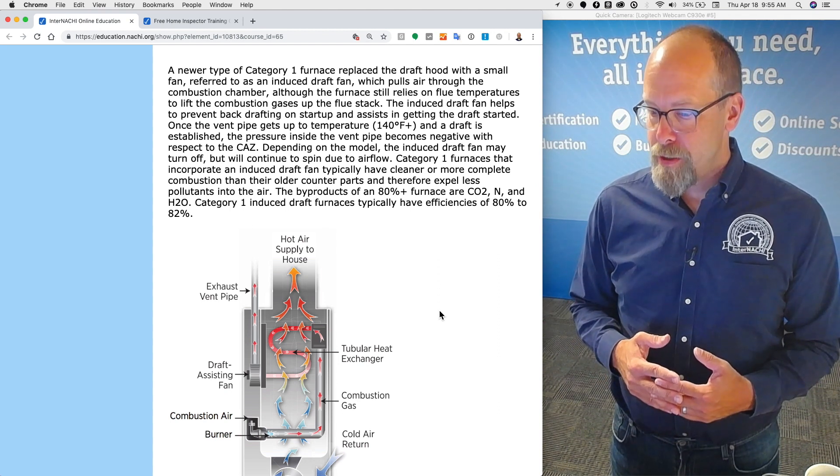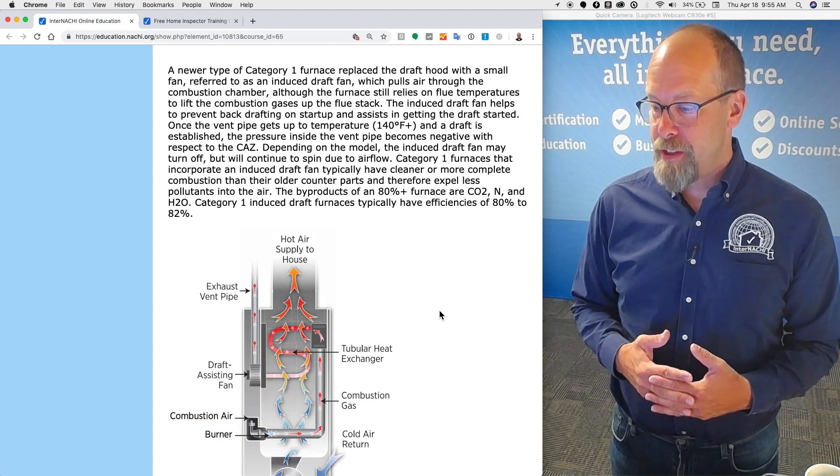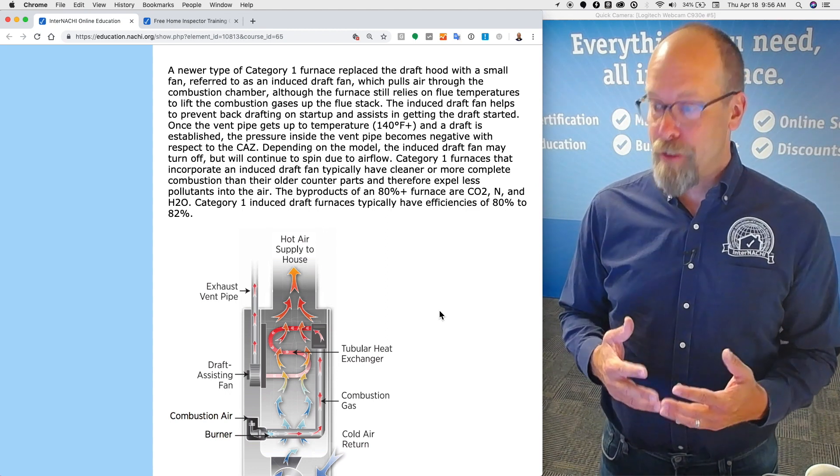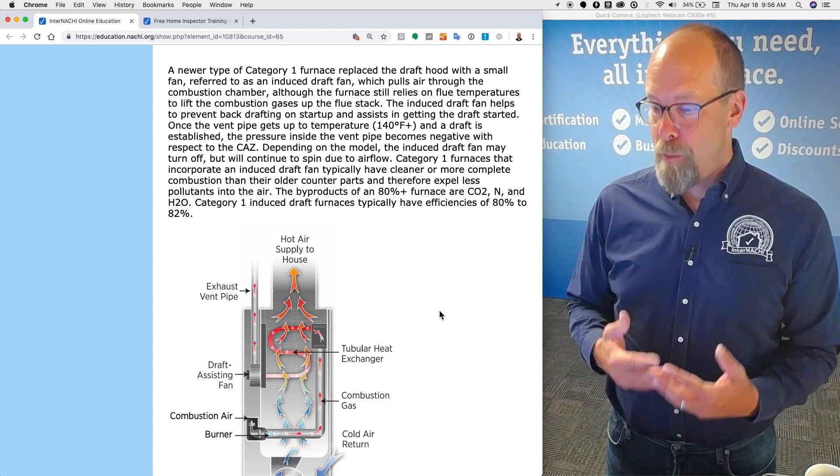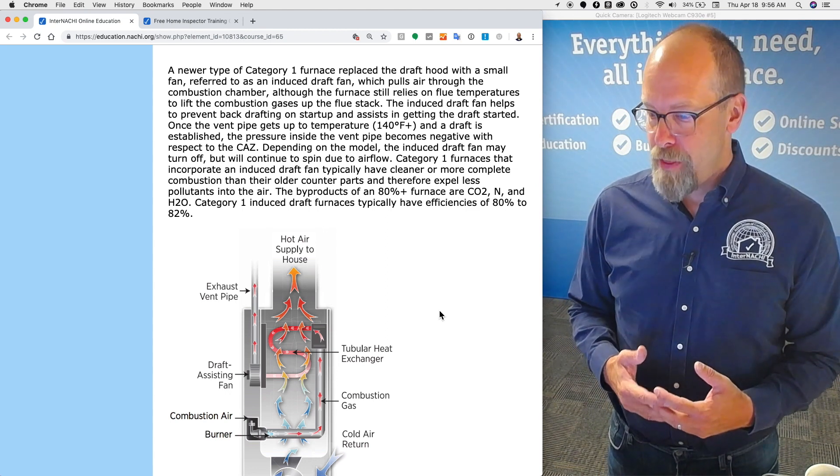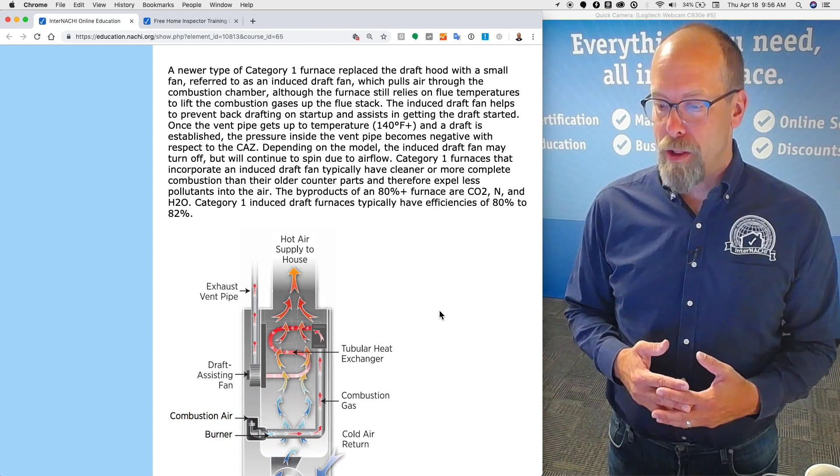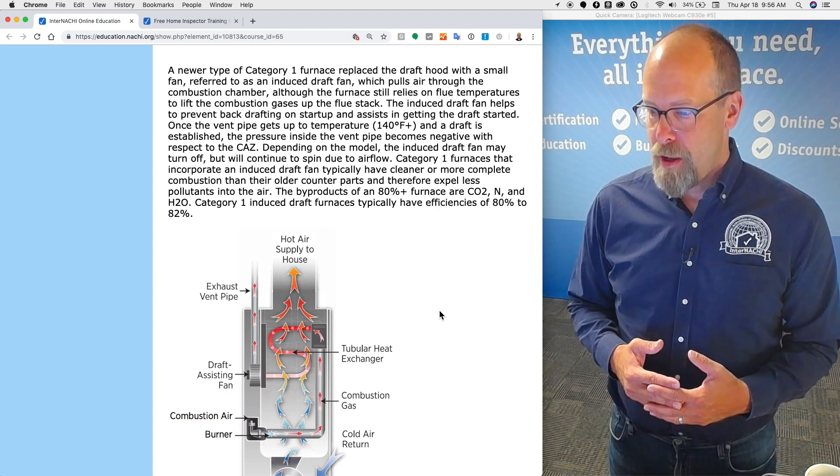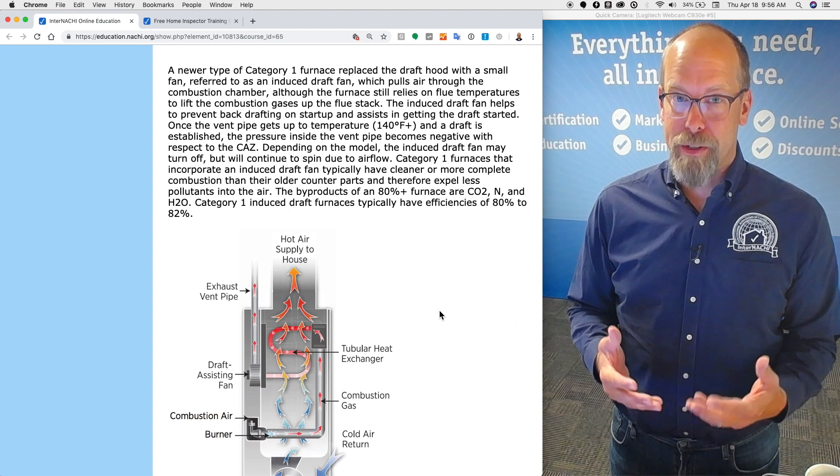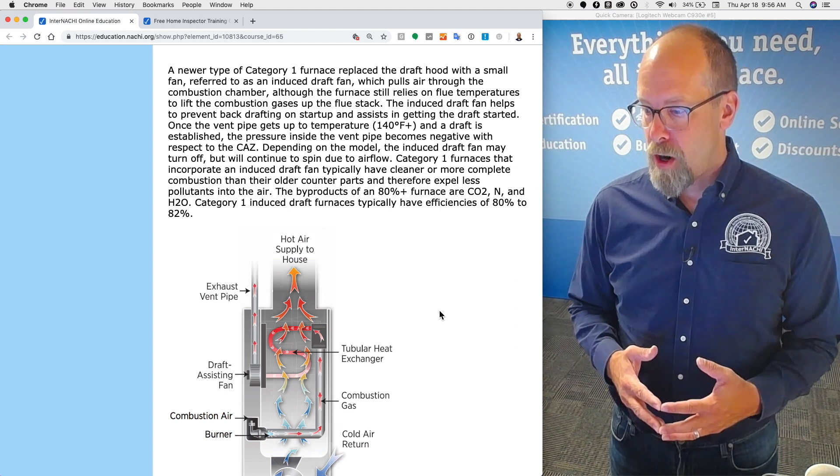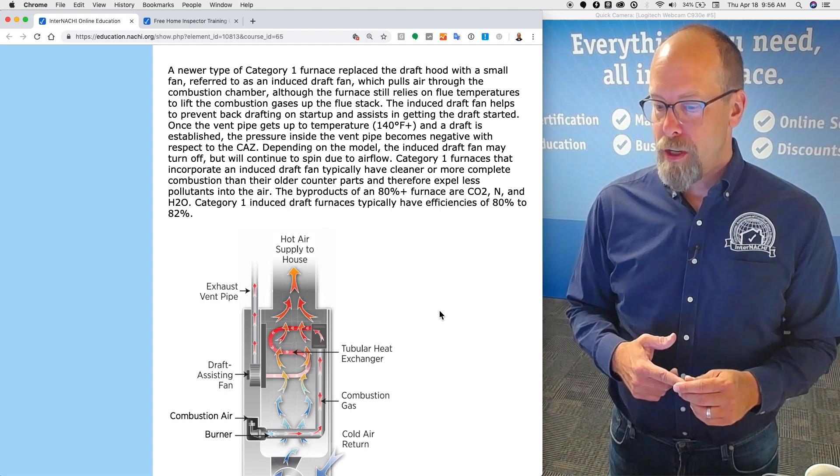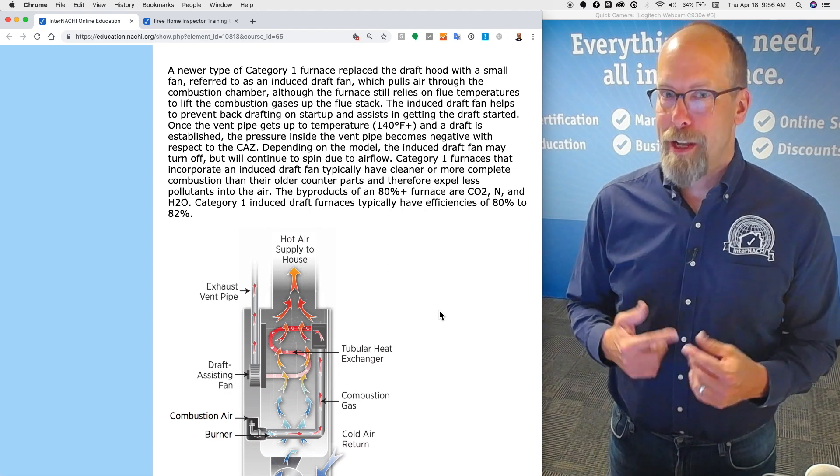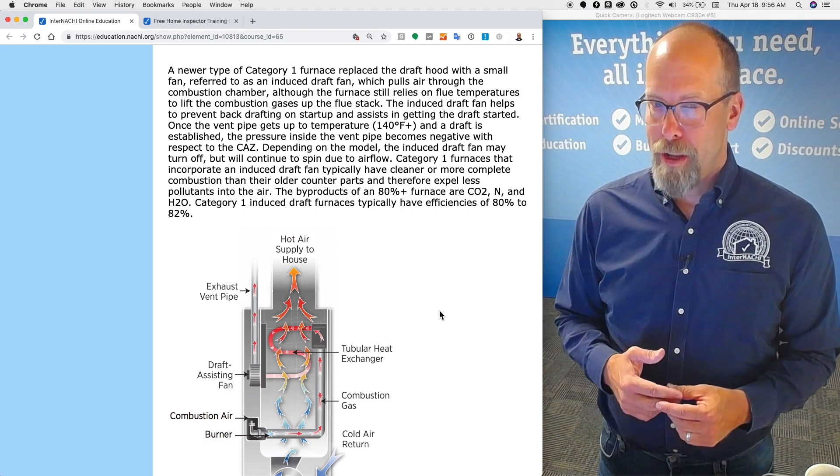Depending on the model, the induced draft fan may turn off but will continue to spin due to air flow. Category one furnaces that incorporate an induced draft fan typically have cleaner and more complete combustion than the older counterparts and therefore expel less pollutants into the air. The byproducts of an 80 percent plus furnace are CO2, carbon dioxide, nitrogen, and water.